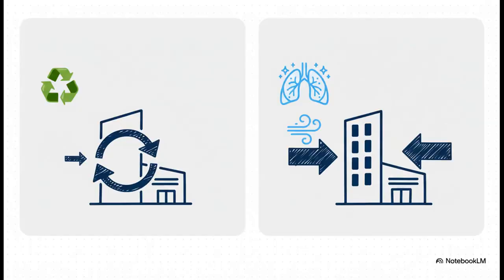So at a high level, the trade-off is pretty clear. Recirculation units, like the name says, reuse the air that's already in the building, and they just mix in a little bit of fresh outside air. This is way more energy efficient, right? Because you're reconditioning air that's already close to the right temperature. On the other hand, you have 100% makeup air units, which are constantly bringing in fresh air from outside. The air quality is amazing, but it comes at a much higher energy cost.